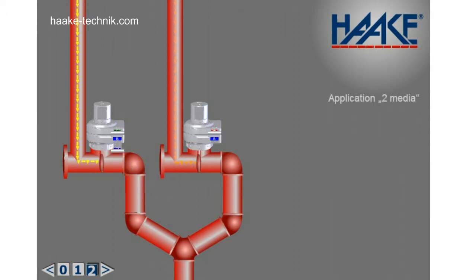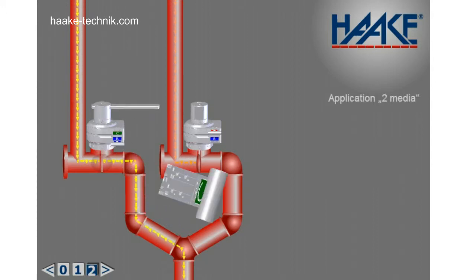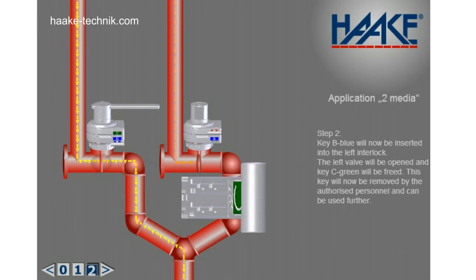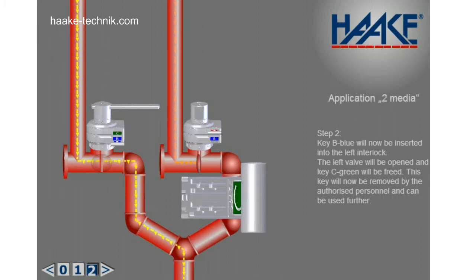Step 2. Key B blue will now be inserted into the left interlock. The left valve will be opened and key C green will be freed. This key will now be removed by the authorized personnel and can be used further.